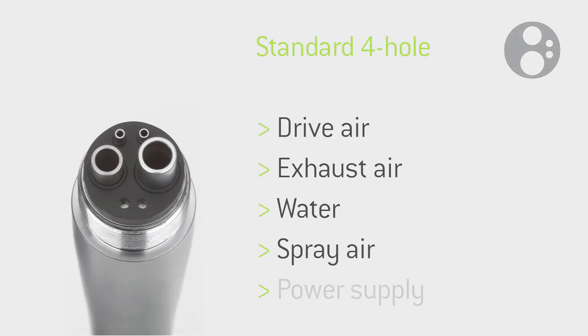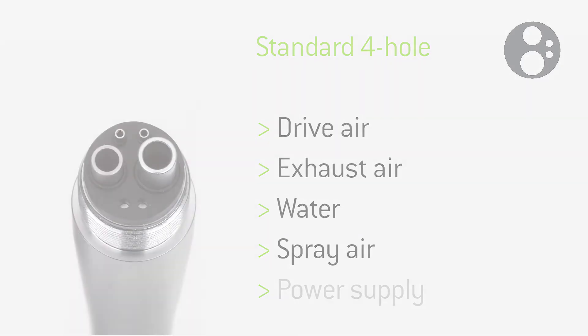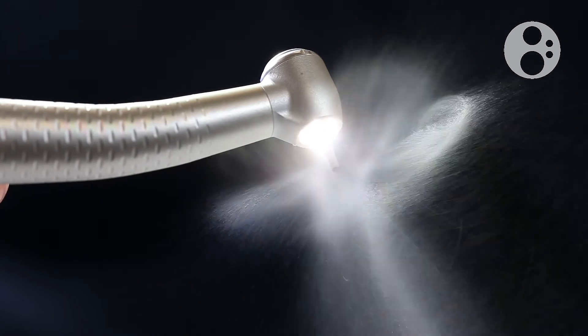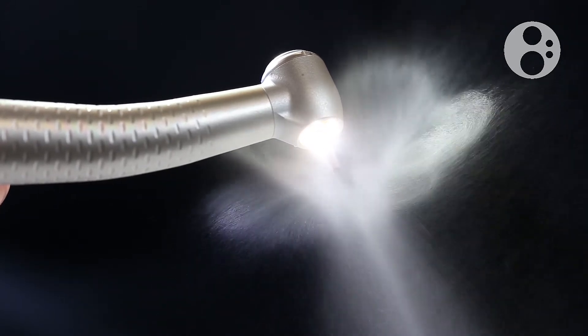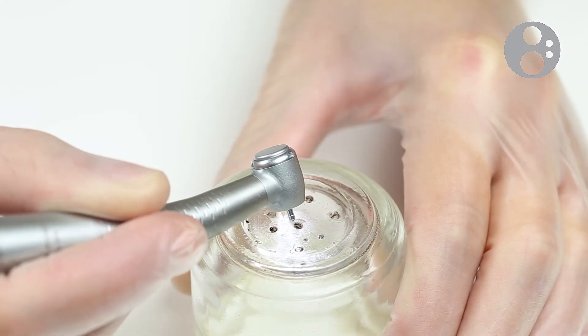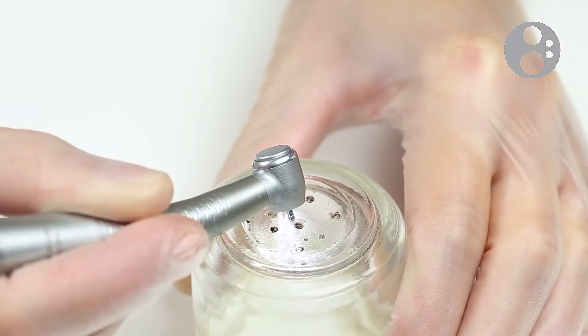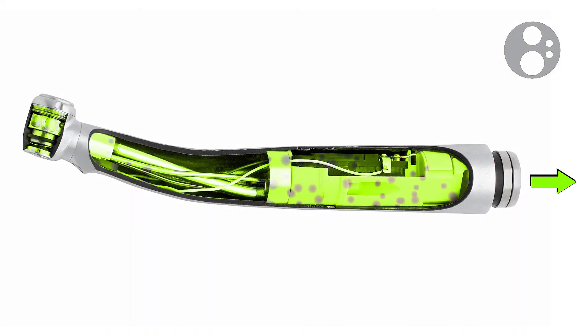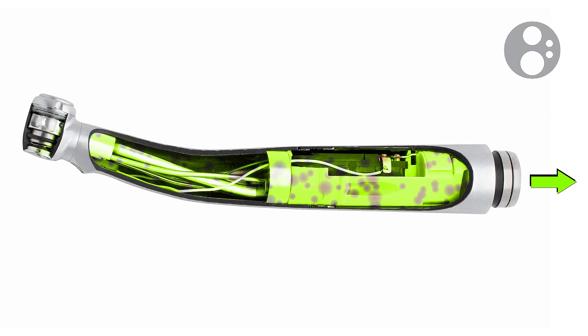The standard four-hole connection has tubes for drive and exhaust air as well as separate spray connections. The amount for the spray can be adjusted separately and set to the user's needs for both water and air. The complete pressure is available for the drive air because air no longer has to be separated for cooling. The removal of the exhaust air means that no air output can be felt by the user of the turbine or air motor, and this air does not come into contact with the treatment site either.